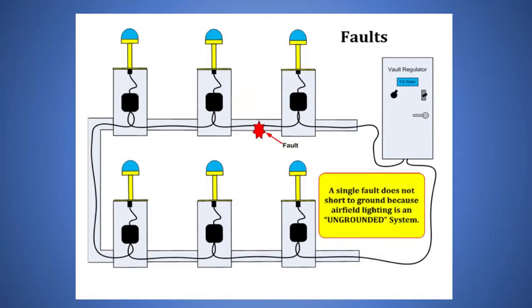Now I know what you're saying. Our system is grounded. We pull a ground wire in every single can and every single conduit on our airfield. Well, just because you're pulling a ground wire in there doesn't mean you have a grounded system. A lot of people don't understand this. And so I think we need to talk about this a lot more here in order to understand how this system works.